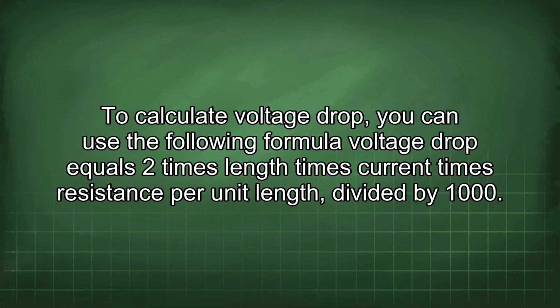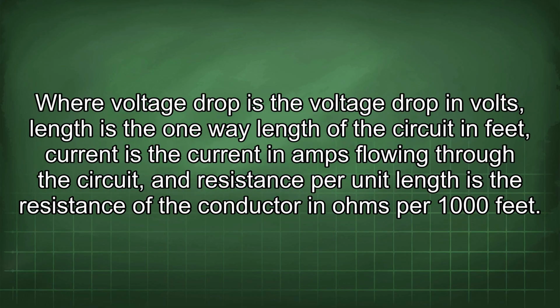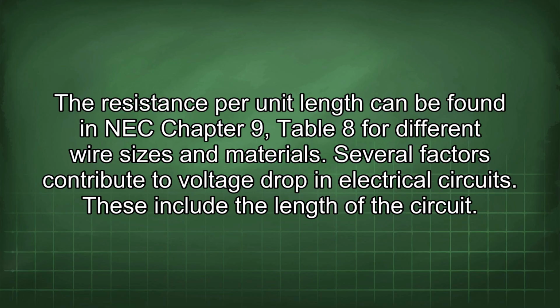To calculate voltage drop, you can use the following formula: voltage drop equals 2 times length times current times resistance per unit length divided by 1000. Where voltage drop is the voltage drop in volts, length is the one-way length of the circuit in feet, current is the current in amps flowing through the circuit, and resistance per unit length is the resistance of the conductor in ohms per 1000 feet. The resistance per unit length can be found in NEC Chapter 9, Table 8 for different wire sizes and materials.